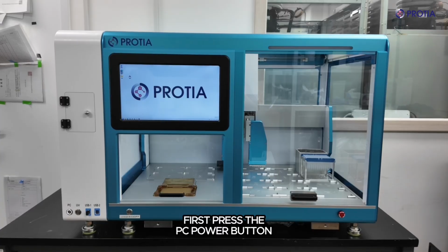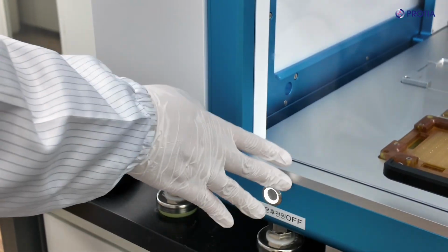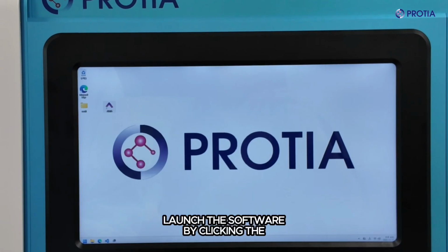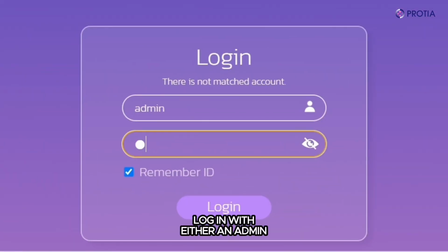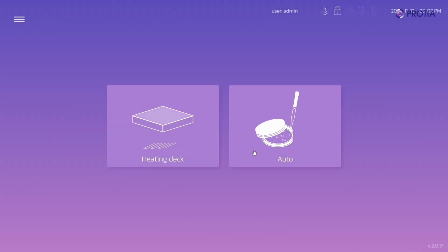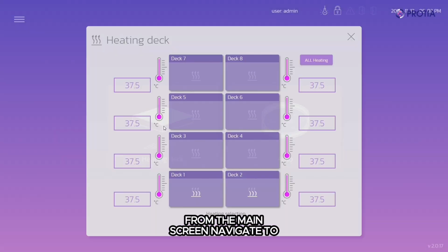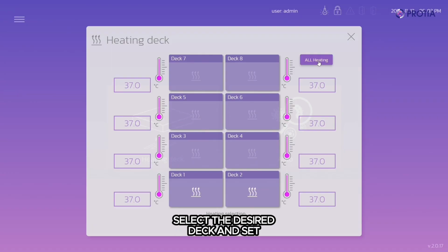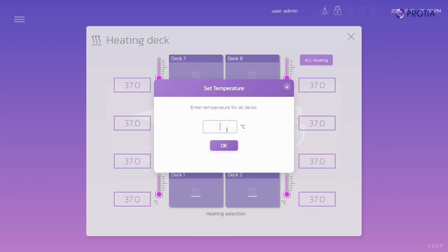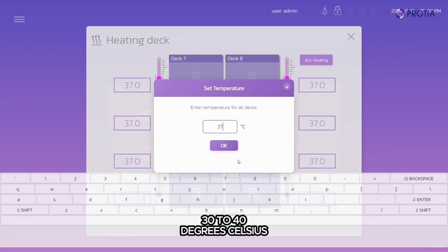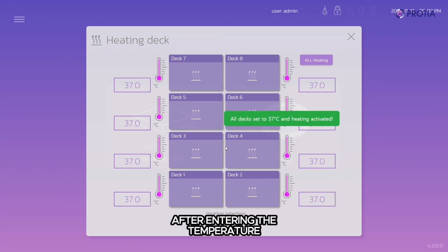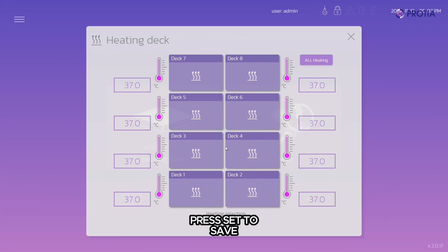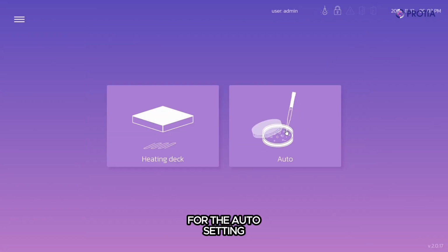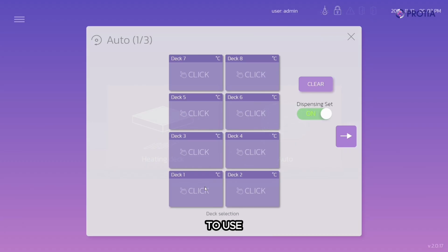Let's begin. First, press the PC power button. Then, press the main unit power button. Launch the software by clicking the icon on the desktop. Log in with either an admin or operator account. From the main screen, navigate to the heating deck menu. Select the desired deck and set the temperature. Each deck can be set between 30 to 40 degrees Celsius. After entering the temperature, press Set to save. Select the plate deck for the auto setting. For the auto setting, select the deck number you wish to use.